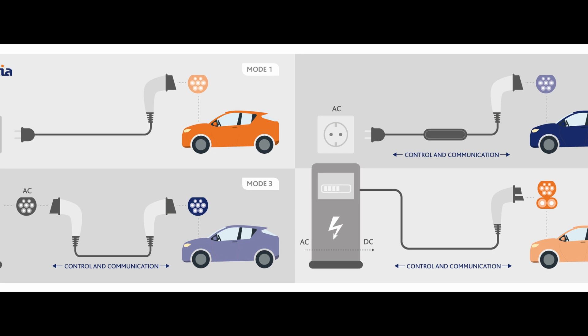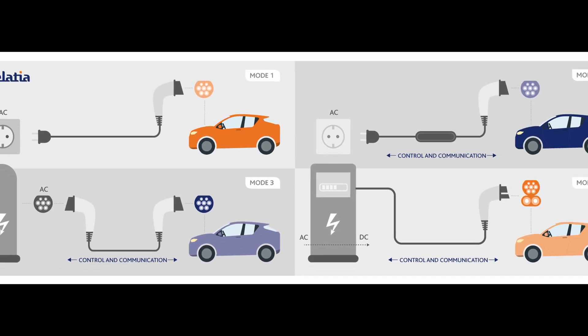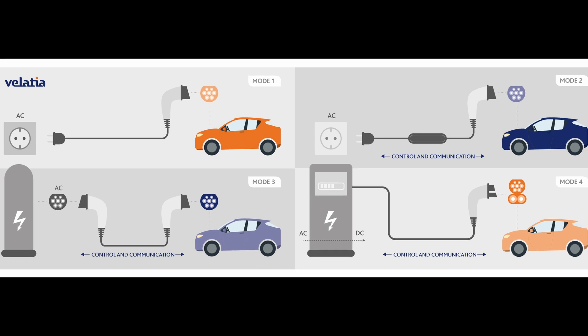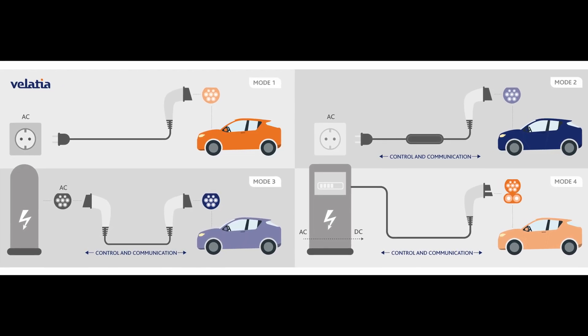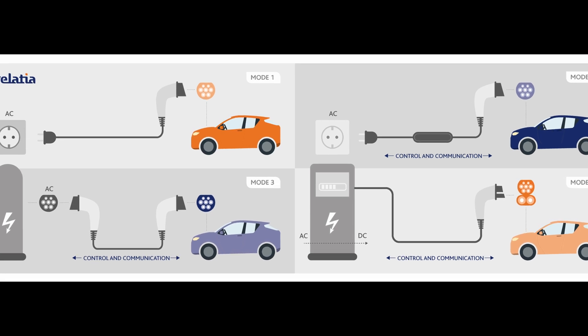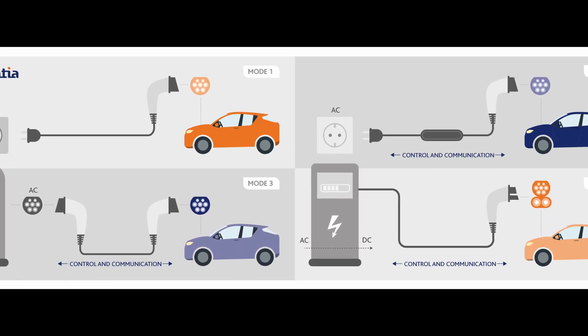We describe four modes in the standard using international terminology for EV charging. Modes one and two are plug-in charging devices and are not permitted for reverse power, so we largely ignore them in this context. Mode three is where you have an AC EVSE on the wall that you plug into your vehicle. Mode four is a DC connection directly from the vehicle to the installation — generally what people think of as fast charging — and both mode three and mode four allow power flow.